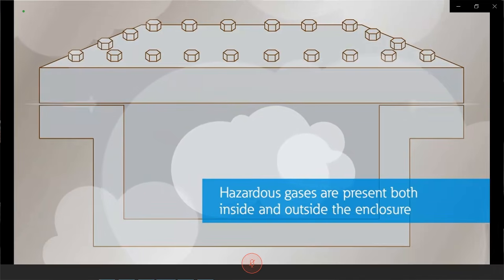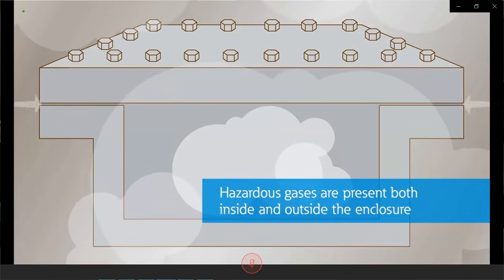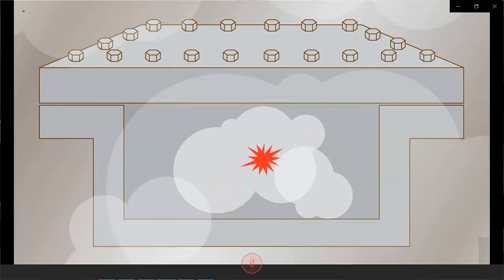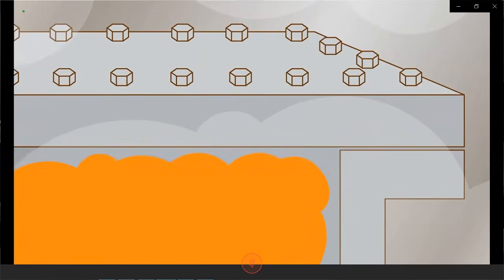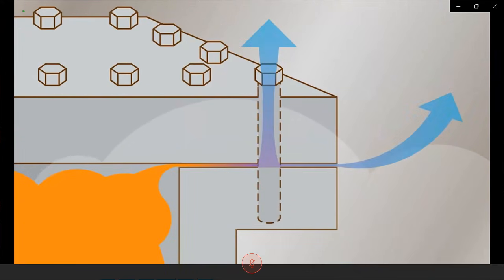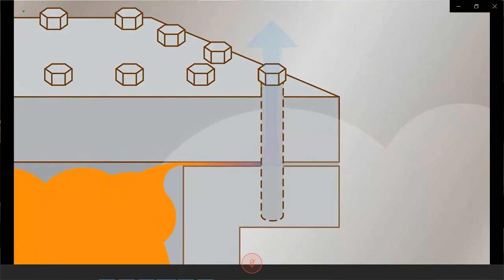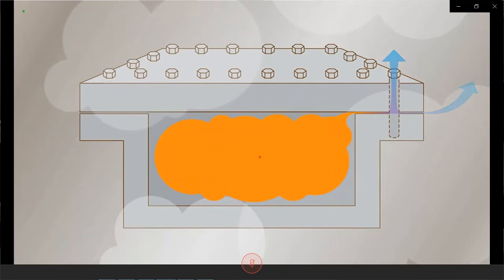All NEMA 7 rated enclosures are constructed to withstand and contain the internal combustion of gases and vapors. They're also designed to cool those hot gases down before releasing them into a hazardous outside atmosphere. This is accomplished via machined flame paths or joints. Properly installed, explosion-proof enclosures are very safe and often deliver decades of reliable service.